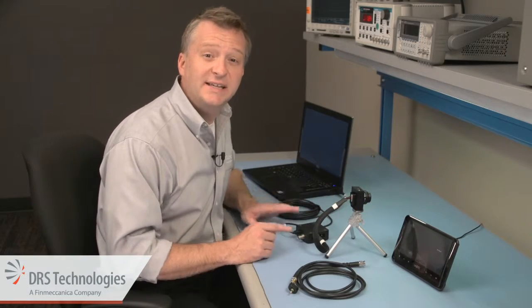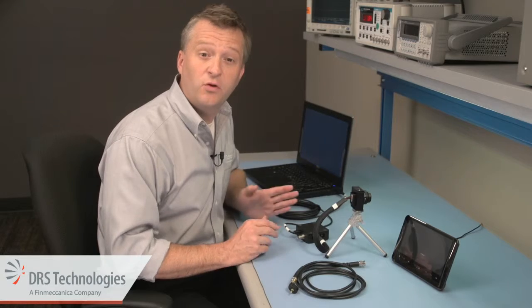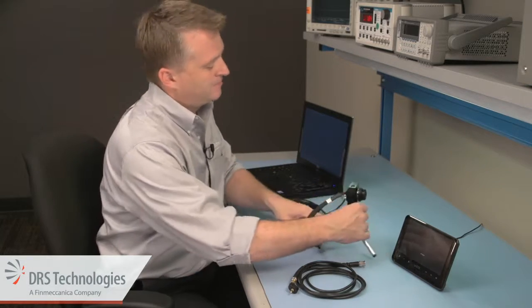That click we just heard indicates the camera is receiving power and has performed a one point calibration. As the camera warms up it will continue to perform one point calibrations to correct for temperature variations.